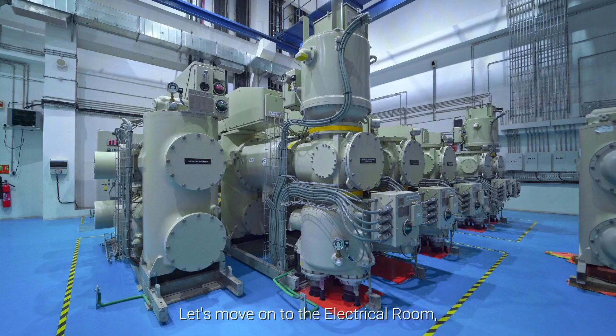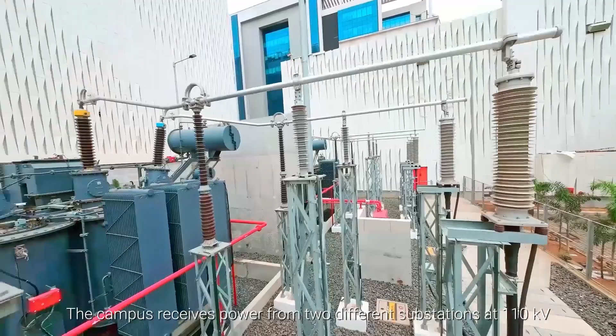The 110 kV panels proposed are of GIS type, consisting of 2 incomer bays, double bus arrangement and 3 outgoing bays for transformers. The campus receives power from 2 different substations at 110 kV. 3 numbers of 30 MVA 110/11 kV power transformers are proposed to cater to the total power requirement of 50 MVA in N+1 configuration. And dual 11 kV feeders will be provided to each building via underground cable, 11 kV panel, working and redundant.